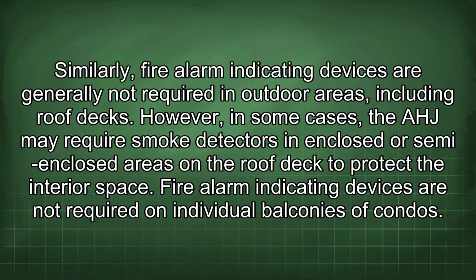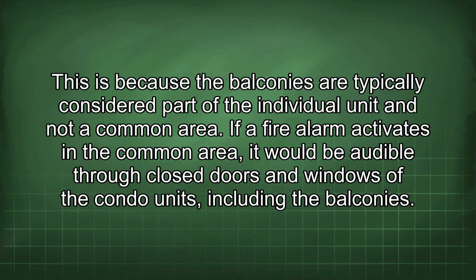Similarly, fire alarm indicating devices are generally not required in outdoor areas, including roof decks. However, in some cases, the AHJ may require smoke detectors in enclosed or semi-enclosed areas on the roof deck to protect the interior space. Fire alarm indicating devices are not required on individual balconies of condos. This is because the balconies are typically considered part of the individual unit and not a common area. If a fire alarm activates in the common area, it would be audible through closed doors and windows of the condo units, including the balconies.